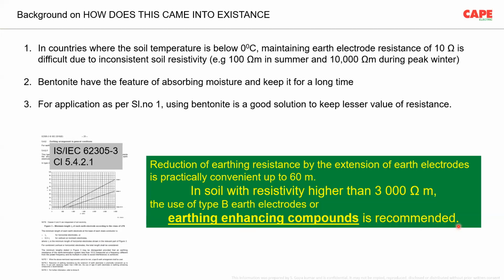So this is the only place in an international standard where this particular material is recommended. Where is it recommended? For lightning protection, where the soil resistivity is more than 3000 ohm meter, you use either a type B earth electrode or an earth enhancing compound. As I said, this is predominantly written because in countries with sub-0 degrees, this material actually helps them in making a resistance lesser than 10 ohm.